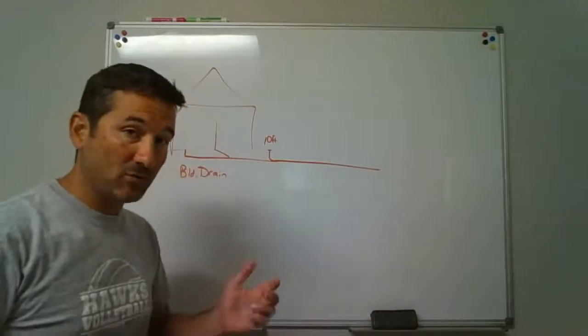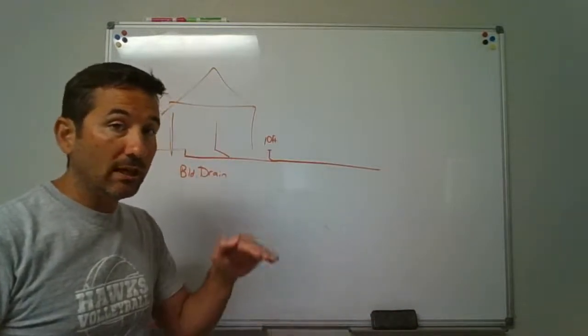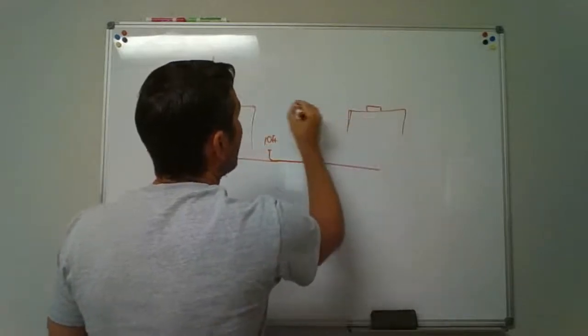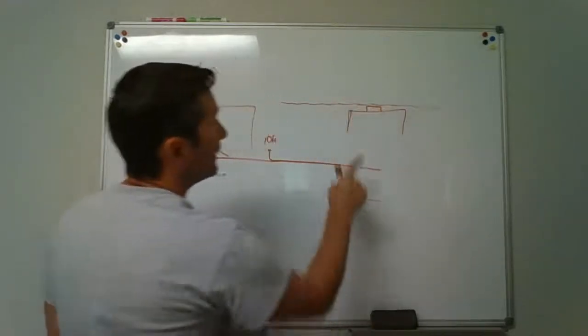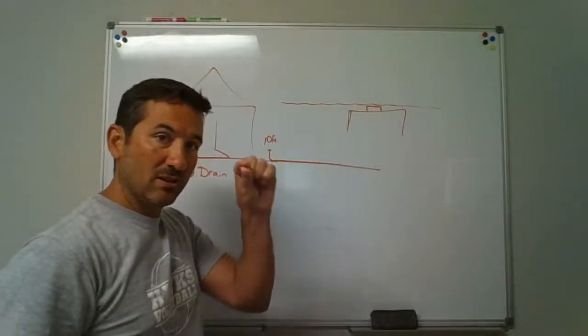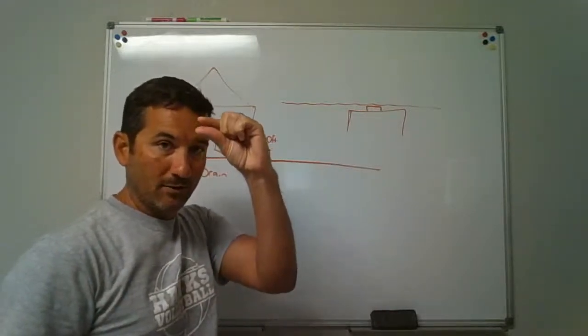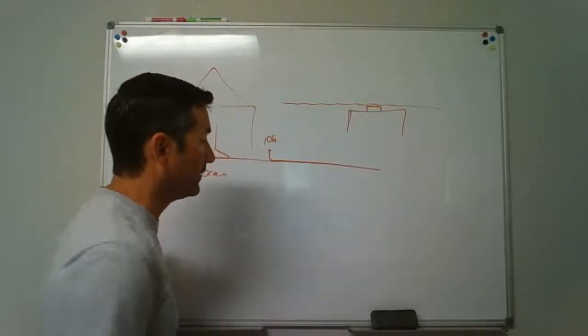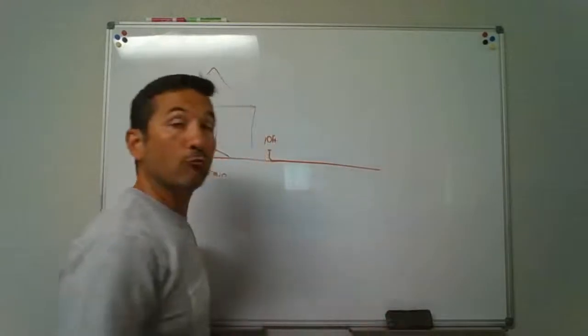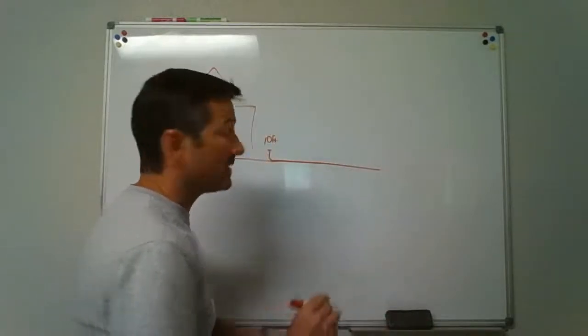But in saying that, if you do have to put it in the yard, if that cleanout gets set a little too low and they final grade over it, and there's your grade, that does not pass code. If it's that far under the ground, it does not meet code. But there's no maximum on it. It can look really, really bad, but it does meet code.